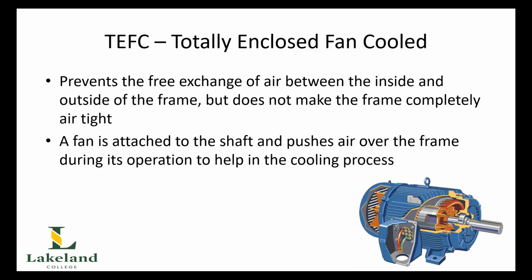So most of the motors that you will see outside are going to be this particular rating. The next one is TEFC, standing for Totally Enclosed Fan Cooled. If you're in Europe, you often see this as TEFV, Totally Enclosed Fan Ventilated. Same thing. These are the ones that you see inside of our power lab, where there is a fan inside of the fan cowling mounted at the end of the shaft, and it will blow air down through the stator and the rotor housings to keep it cool and to remove the hot air from it. So that's the idea of a TEFC motor. Very common, and again, you'll find these ones in our power lab for things like our feed water pumps.